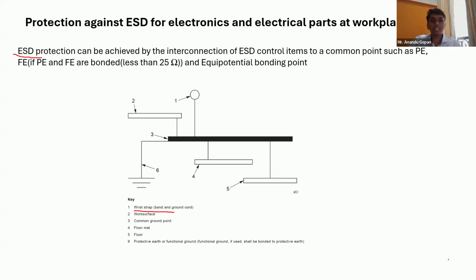When you interconnect everything, they can be connected to your PE conductor, or it can be connected to your functional earthing conductor. But if you connect to a functional earthing conductor, your functional earthing and PE conductor must have less than 25 ohms, which will fulfill the requirement.